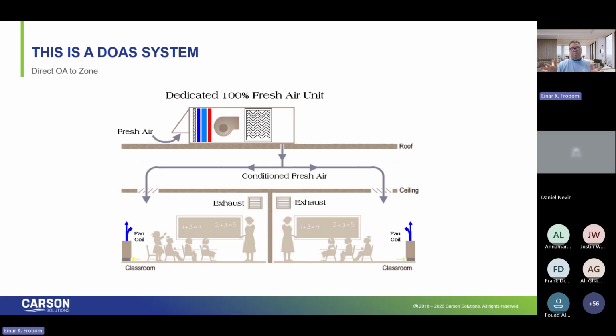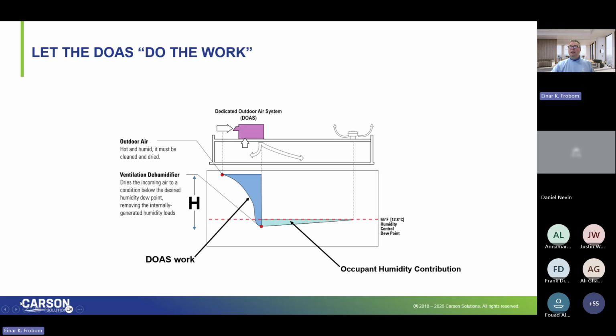The other item, at least as important as the amount of outside air, is the condition of outside air in these systems. So a DOAS unit is a dehumidifier, and in order to truly decouple the biggest loads, the latent loads, which are the outside air first and foremost, but the second largest component of latent contribution is the people. And so if we handle the latent load of the air and the latent load of the people, now our terminal device only has to deal with sensible heating or cooling and not have to deal with an added component of humidity in the space.